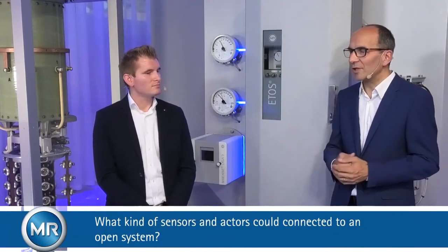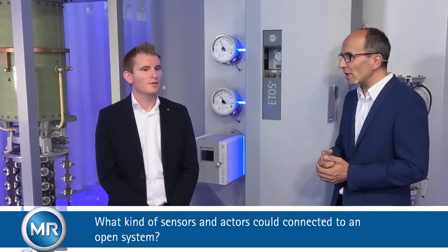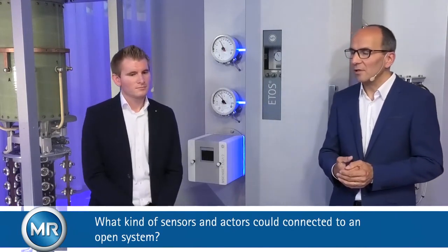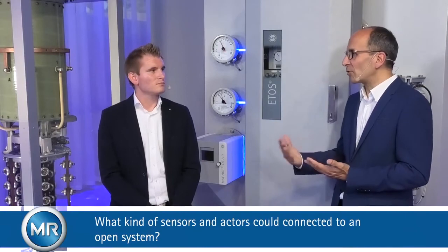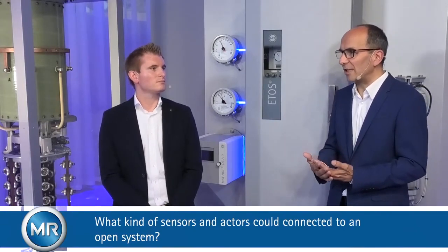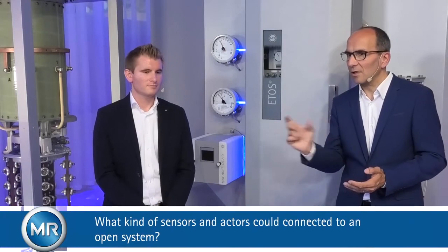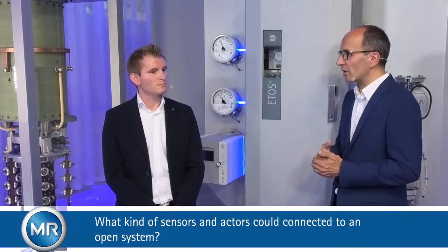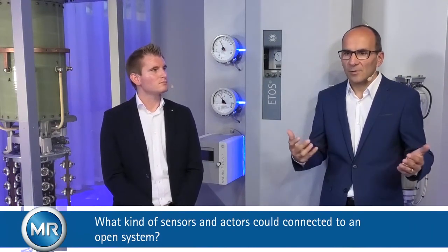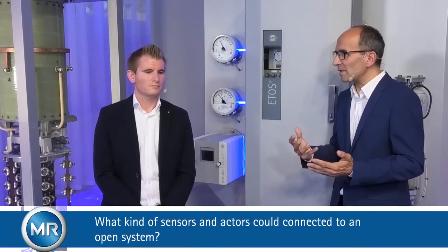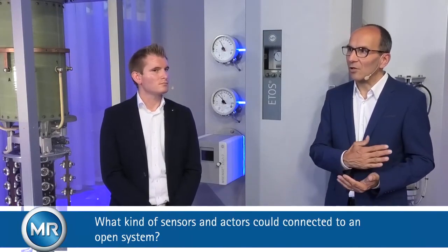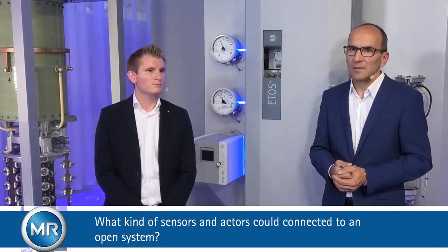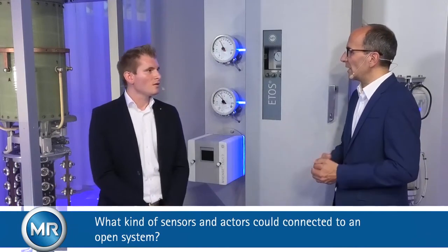For example, bushing monitoring to supervise the bushings, connecting partial discharge monitoring, ensuring that we keep track of all the partial discharge activities within the transformer, and also look at the acceptable range of partial discharge activity. We have the more advanced DGA-9, which tracks all ranges of fault gases. Can you think of additional sensors?